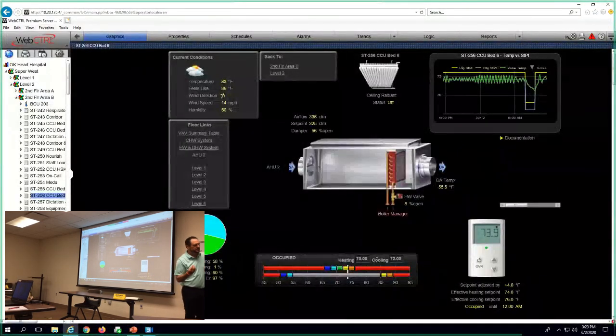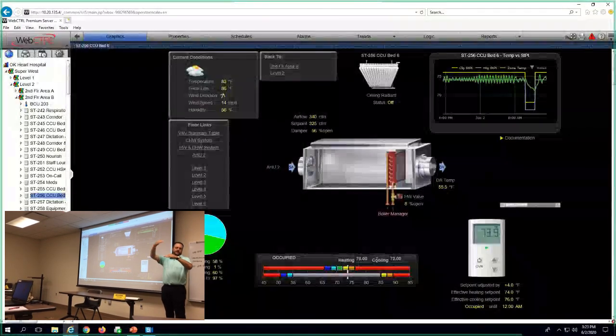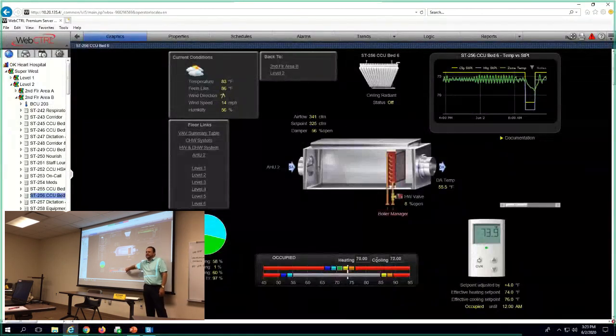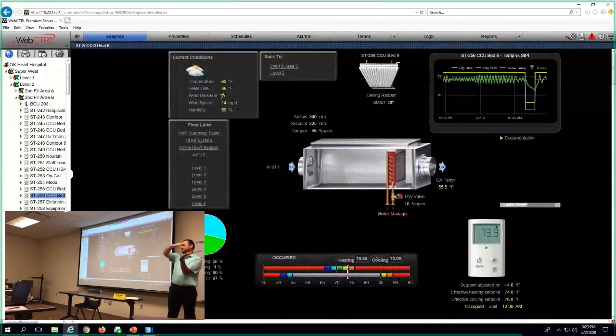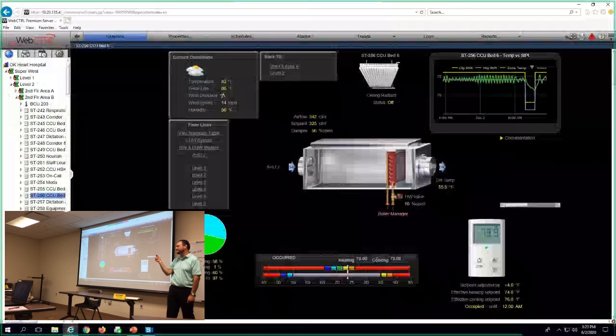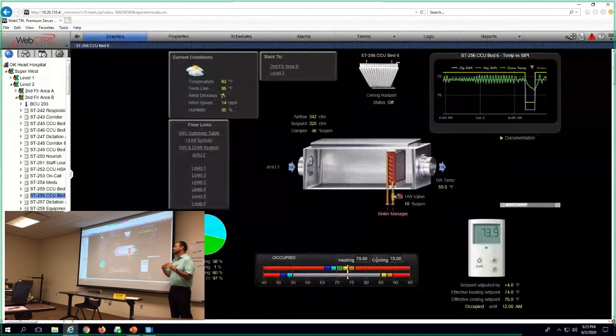What do y'all typically do? I know in the original sequence, and we're gonna look at the sequence here in a little bit, the sequence actually states that they maintain set point and then there's 1 degree above and 1 degree below. But what we ended up with, I was talking with TME when we met a long time ago, was acceptable because it gives you the same thing, it's just where does this need to be set? So a lot of facilities, we set these to 75 and 70, 74 and 70, but essentially if we set it to 70 and 72, it's the same thing as having a set point at 71 and then having your up 1 and down 1, right? Again, it's a little different than what you guys have done in the past, but it should give you the same results. And it allows us to then give you the status colors and diagnose the space.